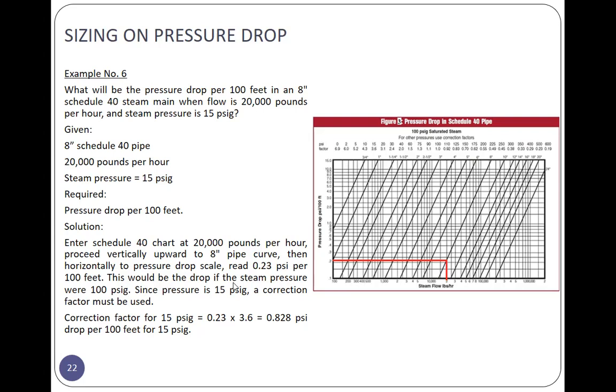So this would be the drop if the steam pressure were 100 PSI gauge. Since the pressure is 15 PSI gauge, the correction factor must be used. So for 15, the factor is 3.6. So your value is 0.23 times 3.6, which is 0.828 PSI drop per 100 feet for 15 PSI gauge. That is your answer.